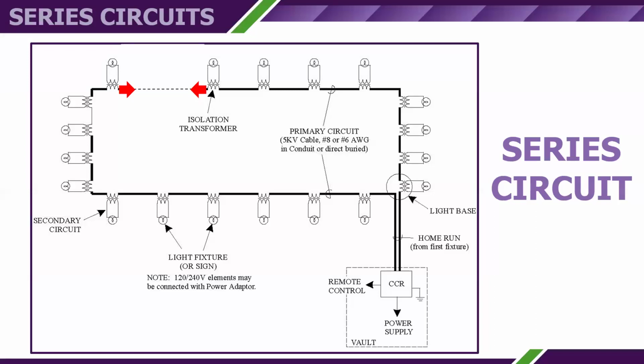So again, you want to make sure we do not complete the circuit. If a constant current regulator can raise the voltage high enough without tripping the overvoltage sensor, the CCR will continue to provide power to the circuit. The CCR simply thinks that you and I are part of the increased load. We do not want to work on energized circuits. We want to make sure that we do not complete the circuit. And again, the CCR will increase the voltage until it reaches the overvoltage point by tripping, trying to maintain 6.6 amp current flow.